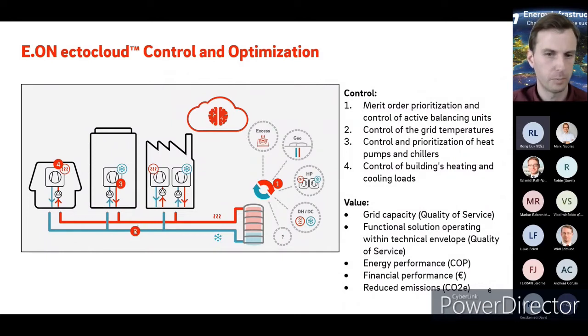A very important aspect is also varying the grid temperature in a way that we get the highest possible efficiency in all of the substations, and also so that we reduce the losses in transmission, and also so that we are able to harvest these low temperature energy sources. So there are multiple aspects of how you ideally change and vary the temperatures on the grid.